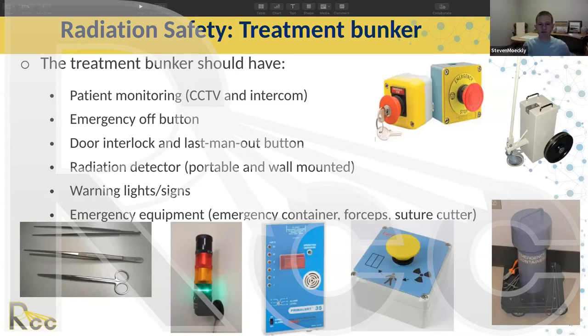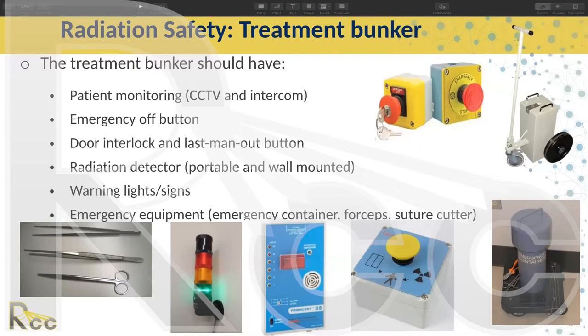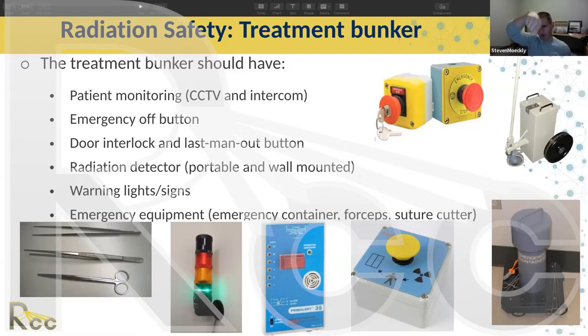For emergency equipment, you want to have an emergency container — we call it a 'pig' in the United States — which is essentially a lead container. You want forceps and a suture cutter. Some people choose long tongs, some shorter forceps. We go for the shorter set because we feel we'd be more adept at grabbing the source wire quickly with them.